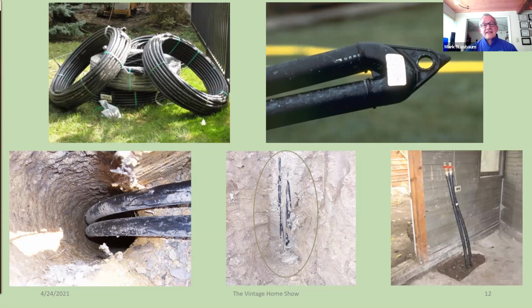This is what the end looks like. This is how we can get two pipes down a 500-foot deep hole. These come in 3/4 or 1.25 inch diameter, and then there's this factory manufactured piece put on the bottom that causes a real sharp turn and good flow. And then this is filled with water and weighted down and inserted in the drilled hole. And it looks like that when it goes into this ungrouted hole. And then we come in and fill it from the bottom up with a thermally enhanced grout, which is just bentonite clay mixed with sand and sometimes carbon and other things to improve the thermal conductivity of the grout.